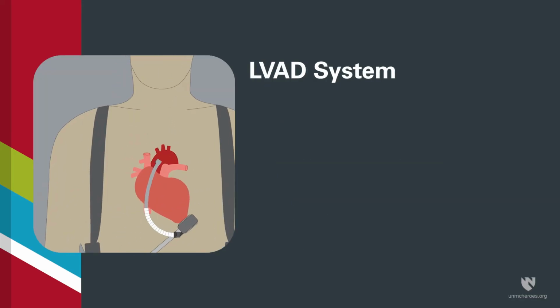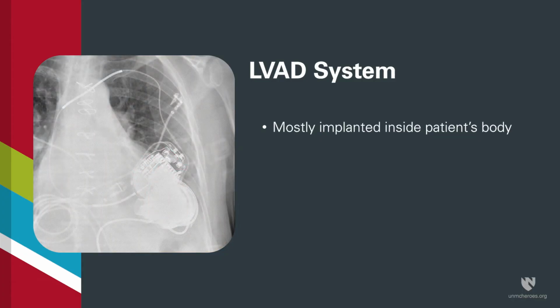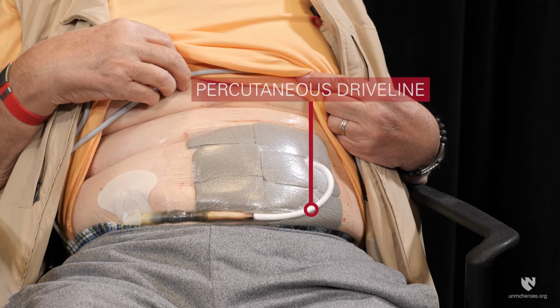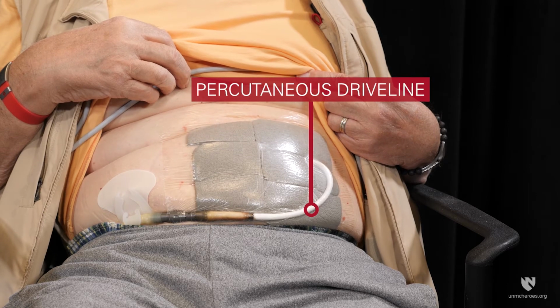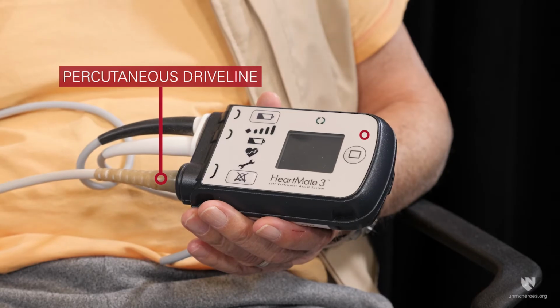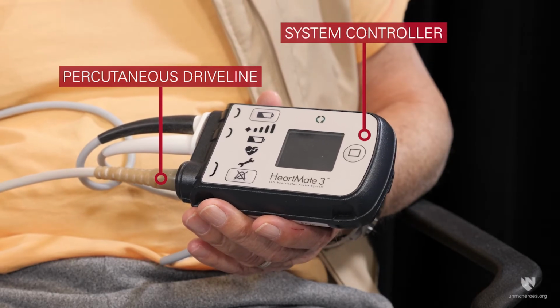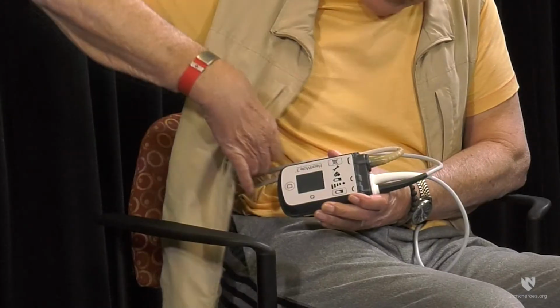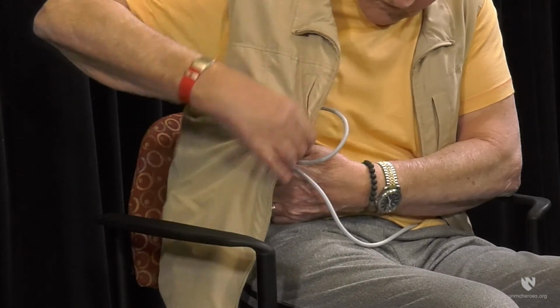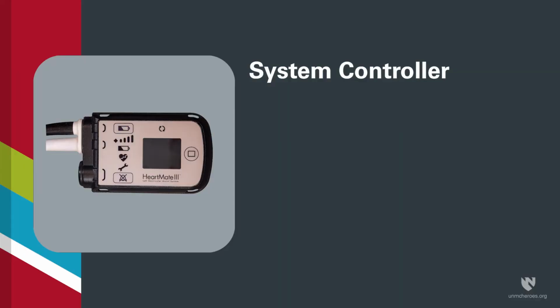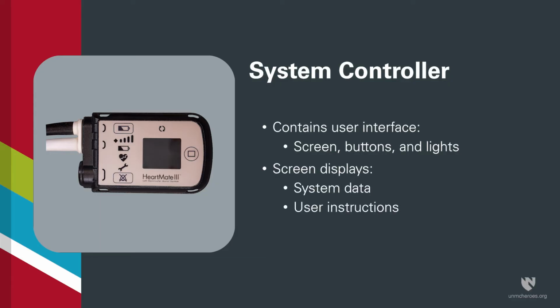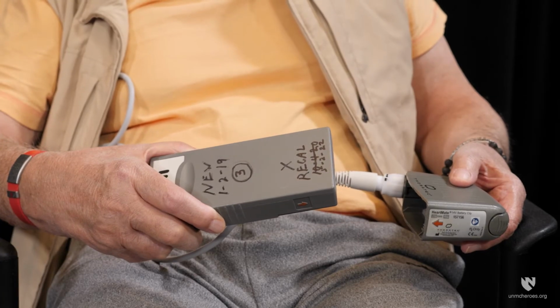When looking at the LVAD system, most of the medical device is implanted on the inside of the body. Visible on the outside of the body is a percutaneous driveline. The driveline connects the pump to the system controller. The system controller is located on the outside of the body and controls the pump. The patient usually carries this in a pocket on a vest, a neck strap, or belt attachment. The system controller contains the user interface, consisting of a screen, buttons, and lights. The screen can display system data, user instructions, and alarms. Alarms are also emitted as audible beeps, for example, when a battery becomes detached.